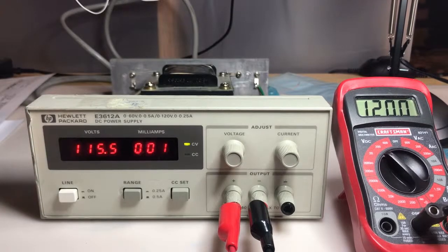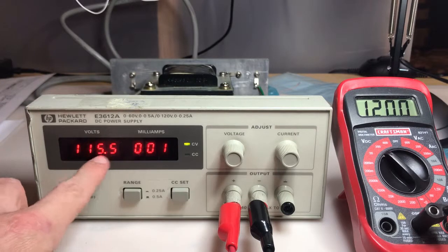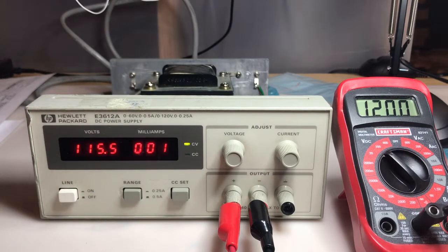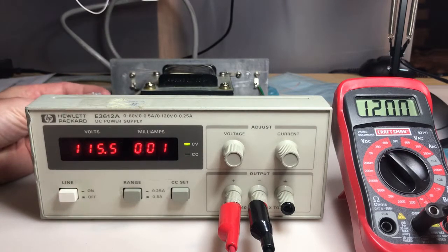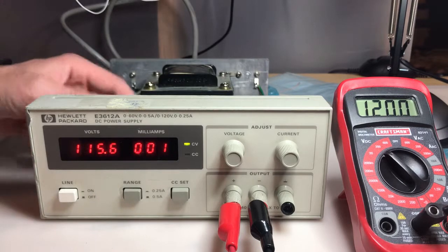Before I hook this up to a load and test the output, I thought I'd calibrate the voltage output first. The service manual says to connect a DVM and multimeter across the output, adjust the voltage in low current mode until the multimeter reads 120, then adjust R10 on the back of the front panel until the front display also reads 120. Found R10, let's adjust.